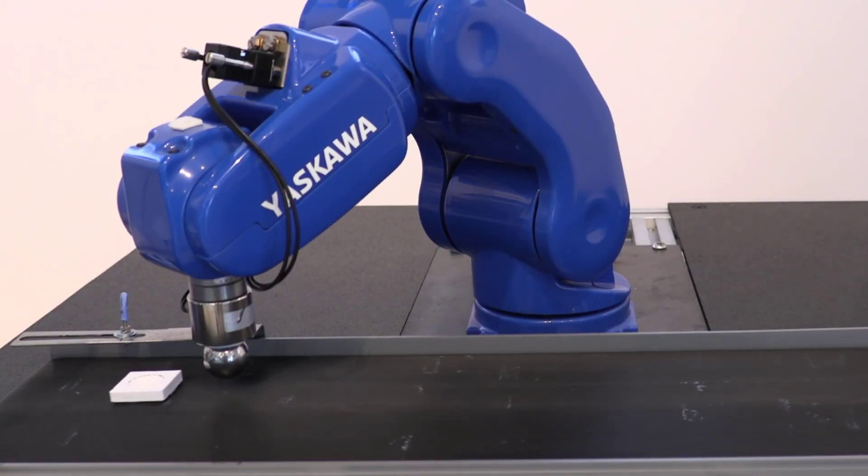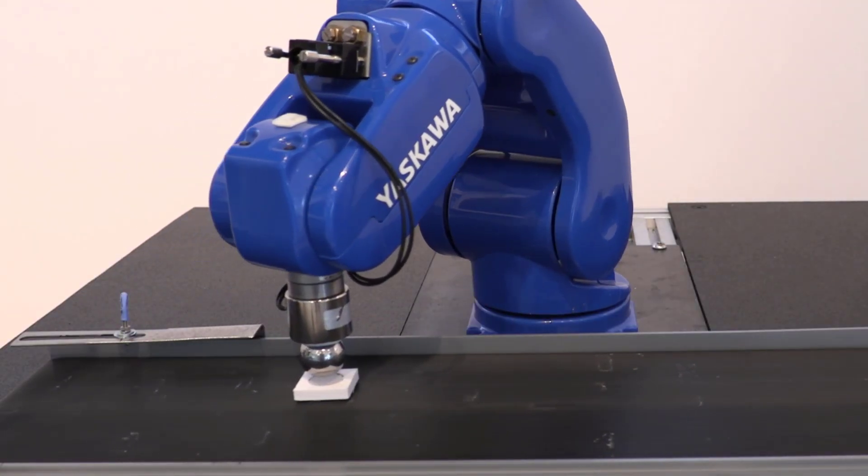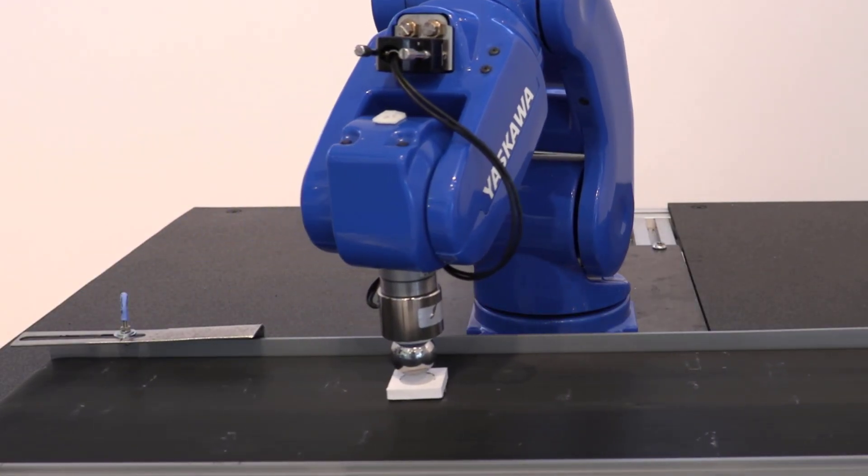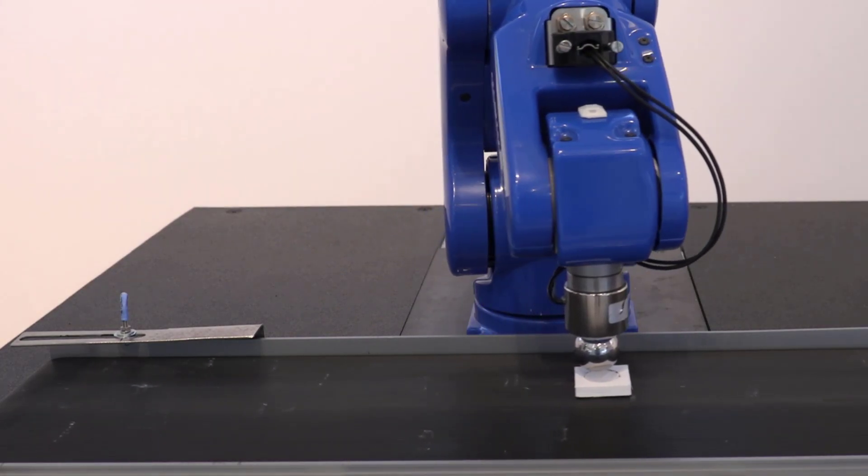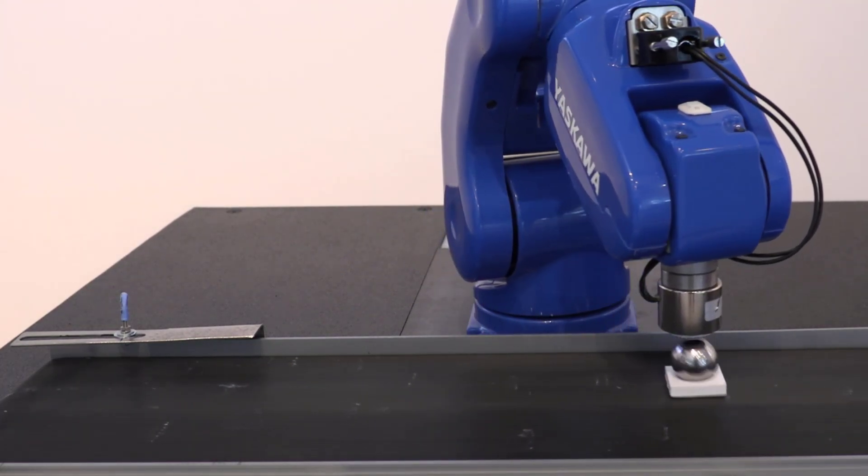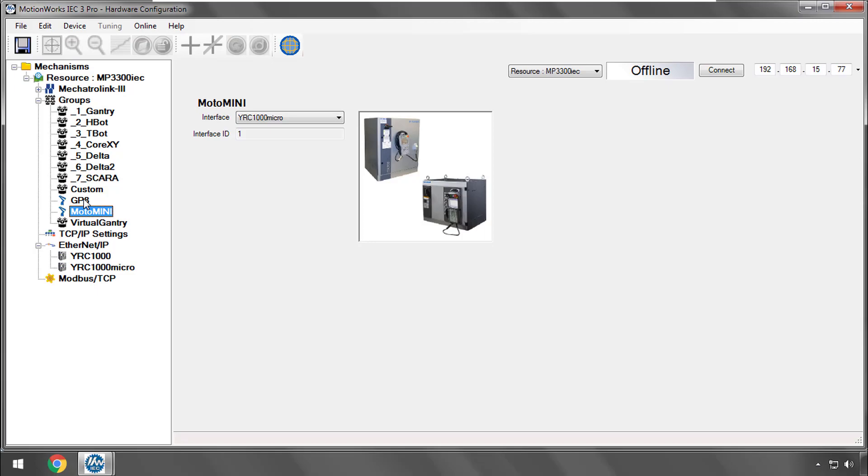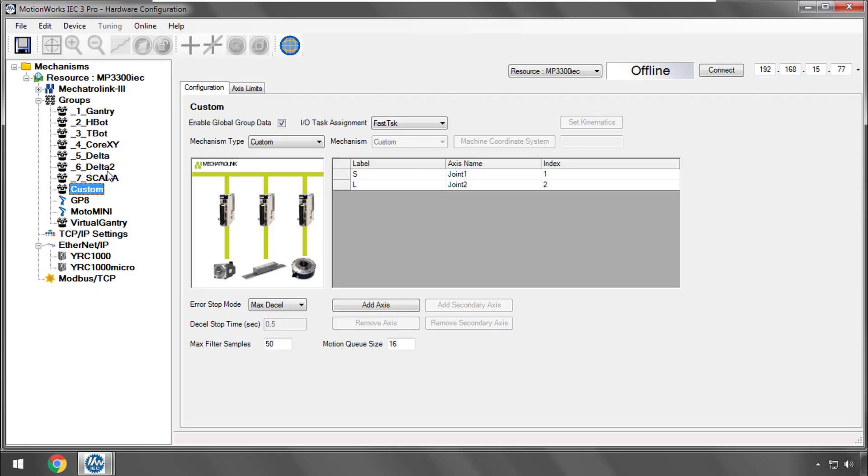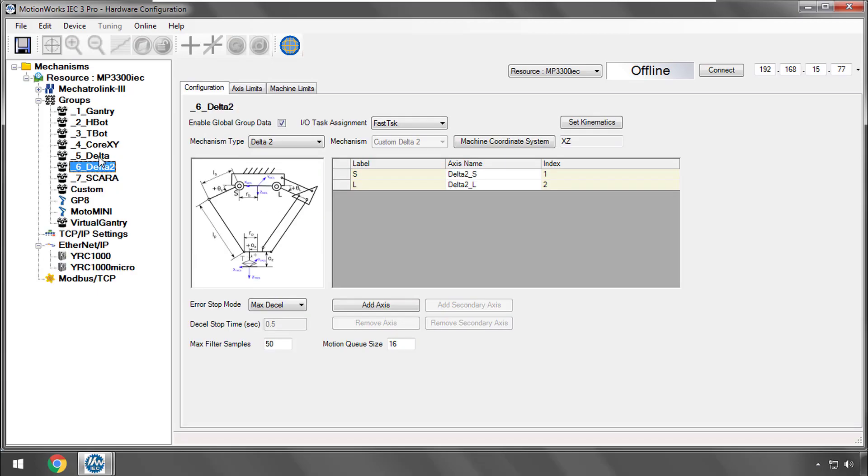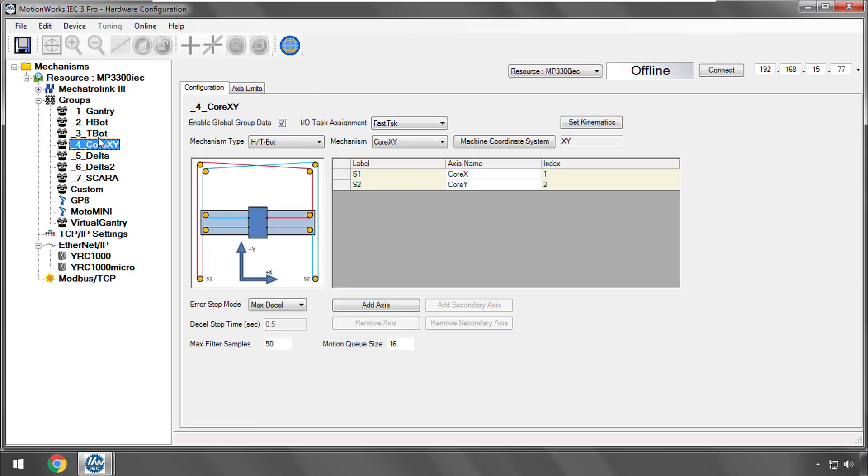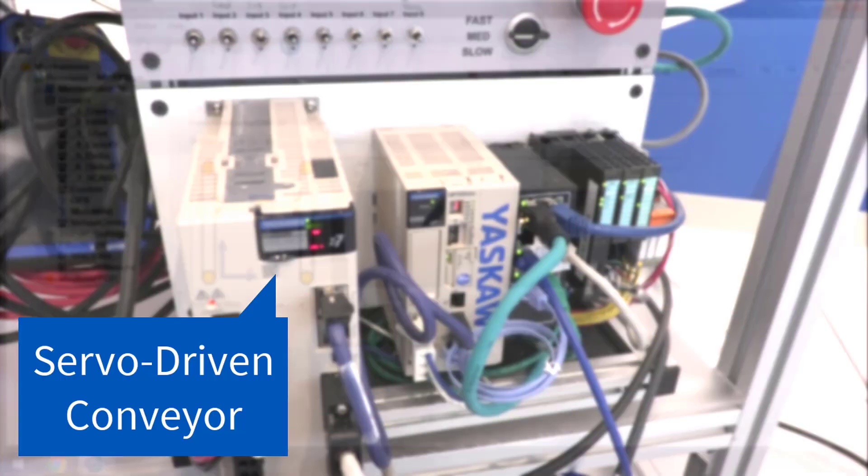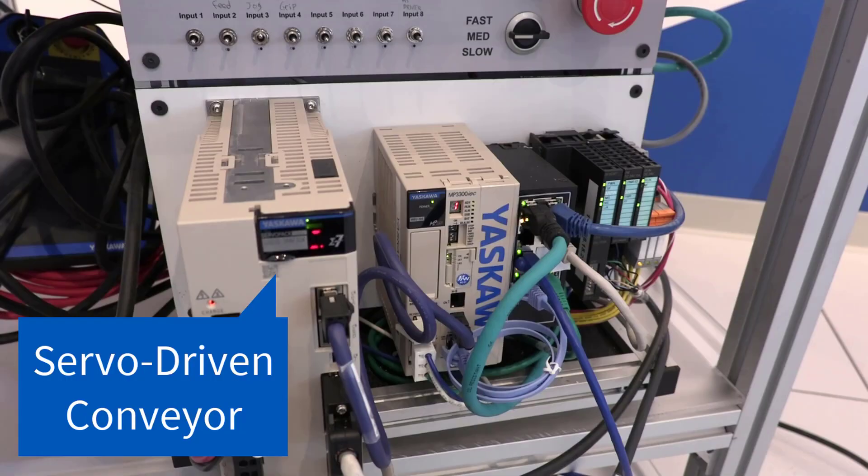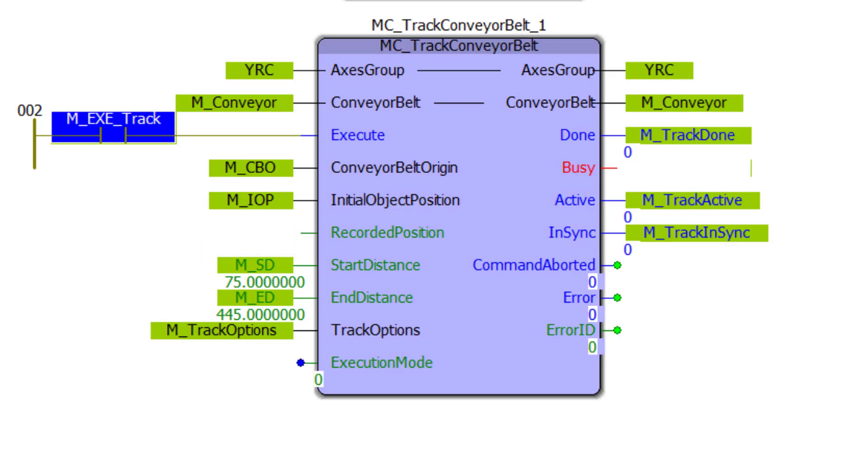Conveyor tracking is designed to improve cycle times for pick and place applications because the belt does not have to stop. It works with all mechanisms and groups supported by the MPIEC series controllers. The conveyor can be controlled directly by a servo, or can be externally driven with encoder feedback. This is all made possible with the function block MCTrackConveyorBelt.